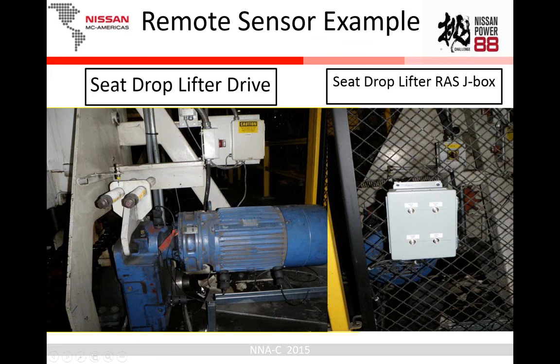Here's a typical remote sensor installation. We have the box outside the cage right here where we can collect the data, and we name our points differently. A lot of people call them inboard and outboard, which is vibration terminology more or less, but we came up with gearbox input, gearbox output, motor front, motor rear terminology. We like to check the input of the gearbox, the output of the gearbox, the motor front bearing, and the motor rear. That's our typical setup.